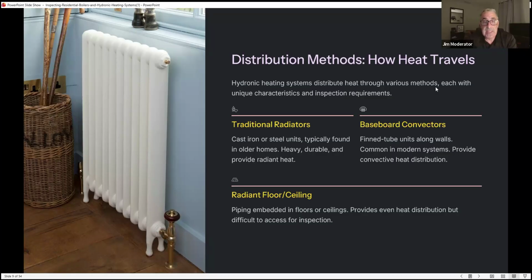So, testing these systems, I have a heat gun. If it's a large house, I keep it right in my pocket and I'll just run around the house to check that there's heat in each room. And I'll know if there are any covers over the radiators, especially if there are going to be kids in the house, and I'll let the client know. A lot of times I'll find that in the master bedroom upstairs the radiators are off and they'll want to know why. I'll say, usually because the room's getting too hot. The radiant heat from the first floor will travel up, and that's most likely enough. And that's why they had the radiator shut off from the top.